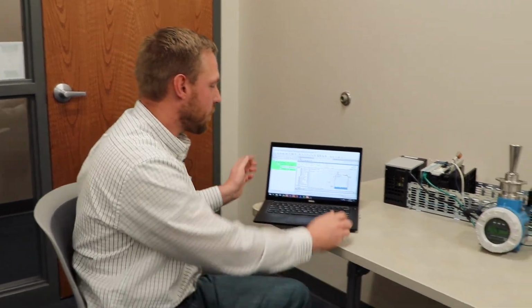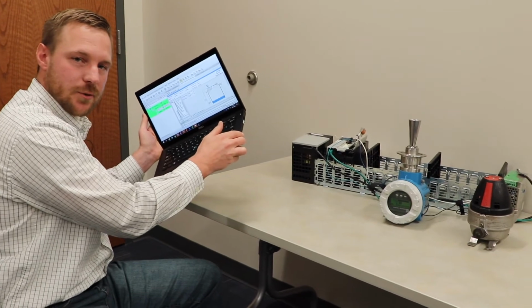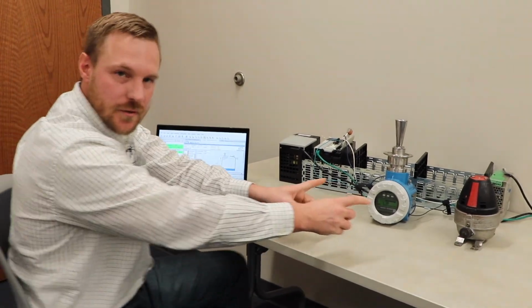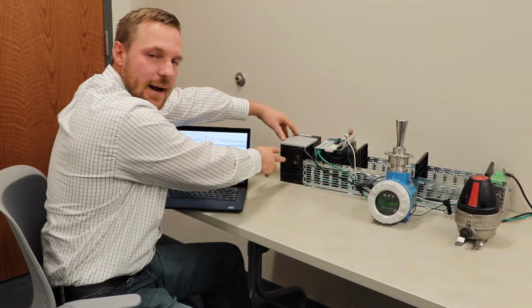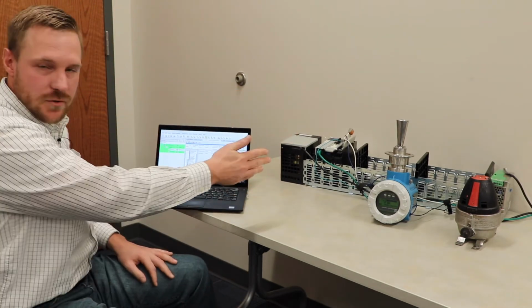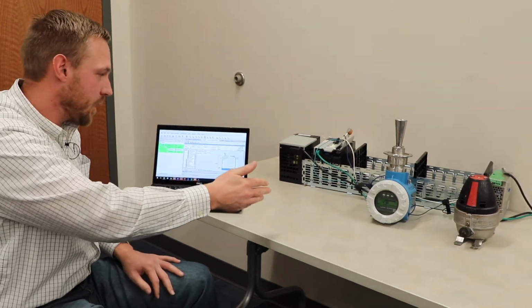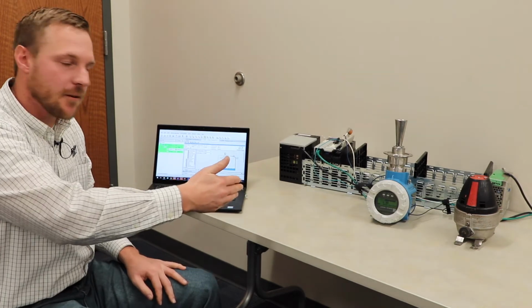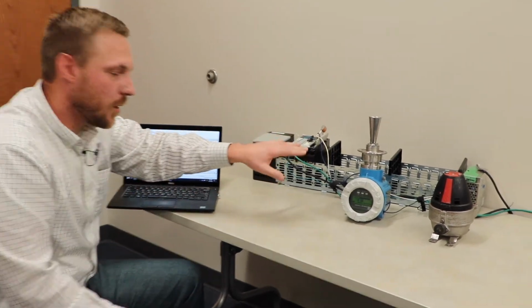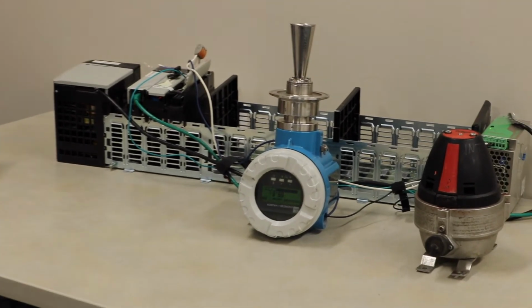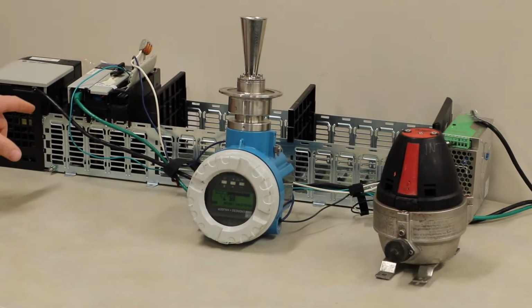Okay, now I'll show you a demonstration of remote HART instrumentation support. Everything we need for it is right here on the table. We've got our laptop that we'll be using to connect to these instruments through this PLC rack. As you see, there's no wires connected, and the only means we have of connection to this equipment is via connection to the network connection that this PLC rack resides on.